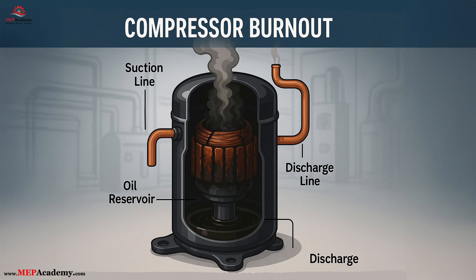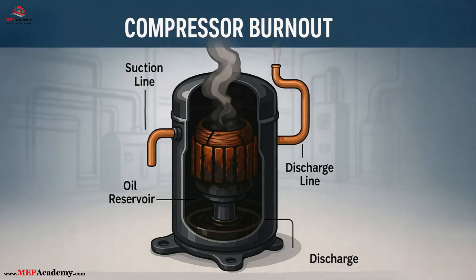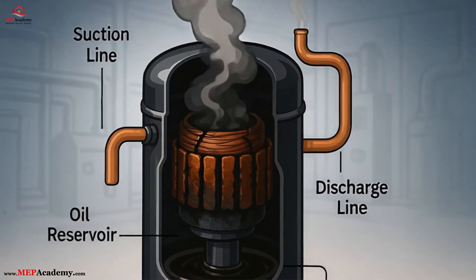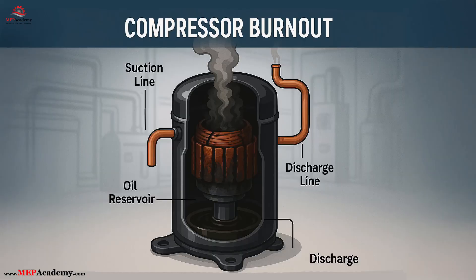Number one: Compressor Burnout – Causes and Symptoms. First on the list, compressor burnout. This is one of the most catastrophic failures in a refrigeration system. A burnout occurs when internal motor windings overheat and break down, releasing acids into the system.